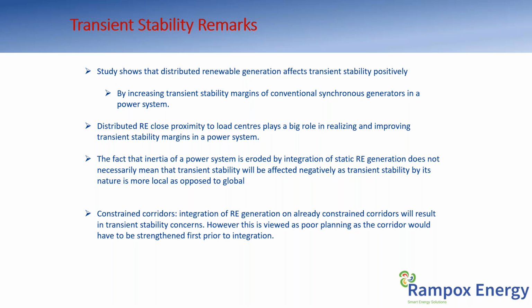I think we have touched on that. The fact that inertia of the power system is eroded by integration of static RE generation does not necessarily mean transient stability will also be affected negatively, as transient stability by its nature is more local as opposed to global. So, constrained corridors, which is what you've seen: integration of RE generation on already constrained corridors will result in transient stability concerns. However, this is viewed as poor planning, as the corridor would have to be strengthened first prior to integration.